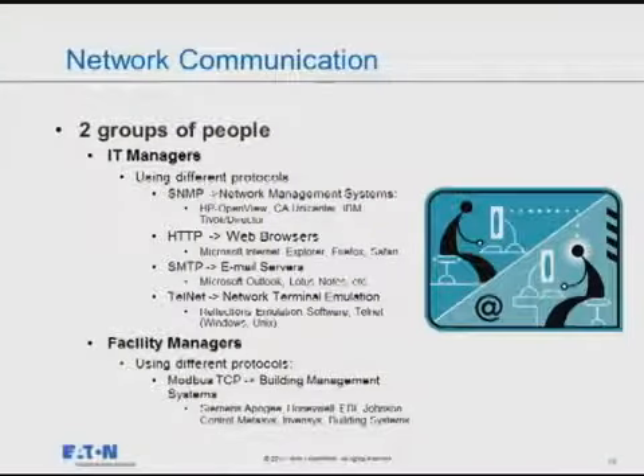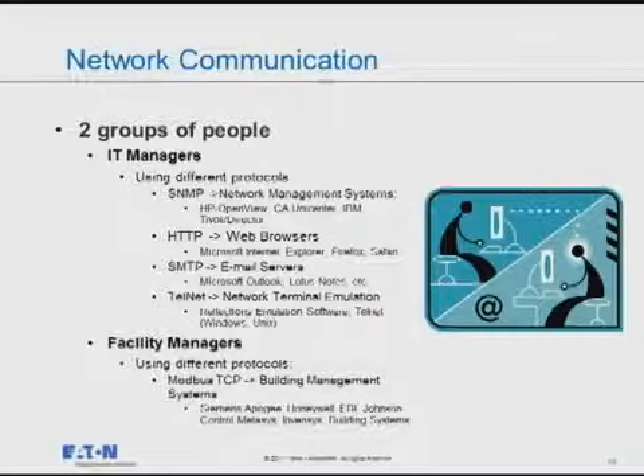Network communications, once we take that leap across the Modbus RTU, introduces two groups of people—and it's one of the most appealing parts of the UPS world for me. I get to talk to facilities, electrical engineers, but also IT managers. There's a big divide in terms of communications and what they're interested in monitoring. The IT community monitors server performance, bandwidth issues, and parameters driven around data processing and communications. The facilities group is really talking about the power itself.